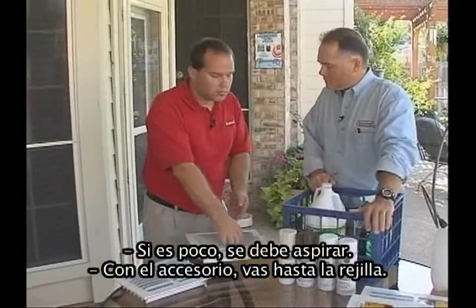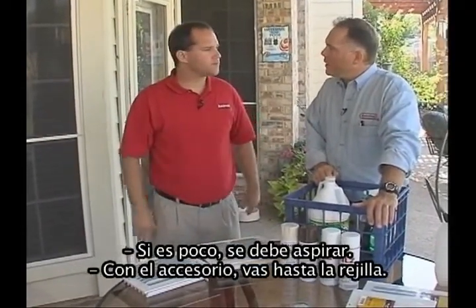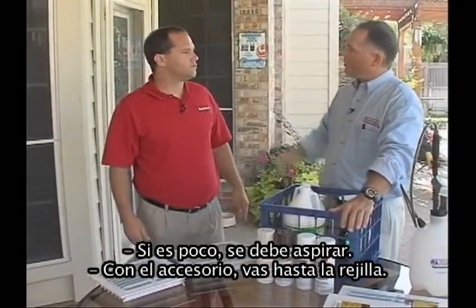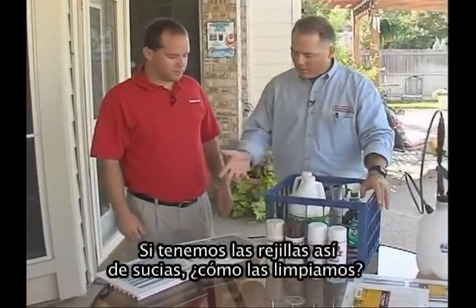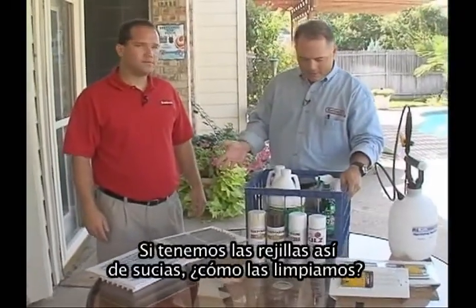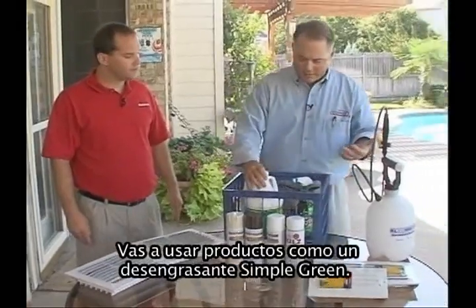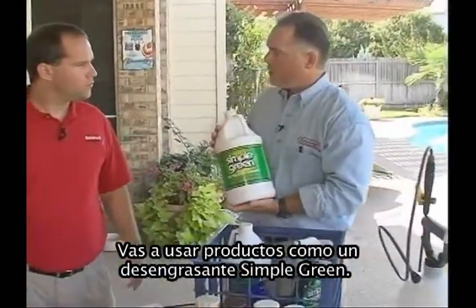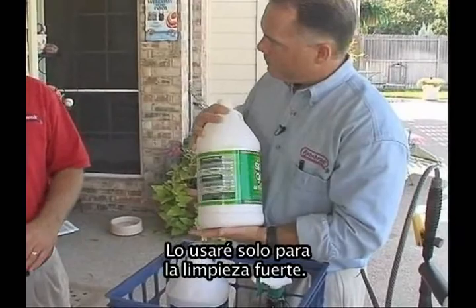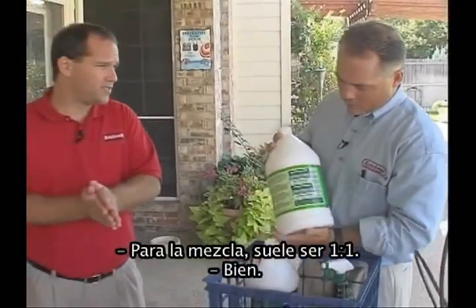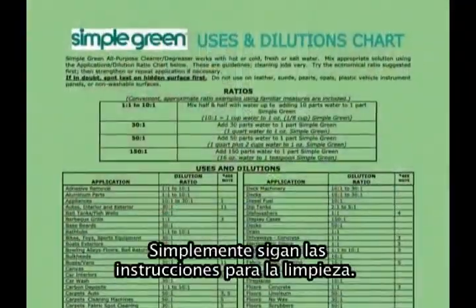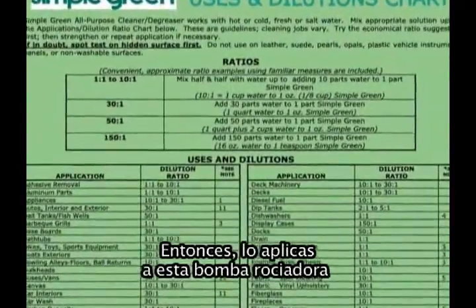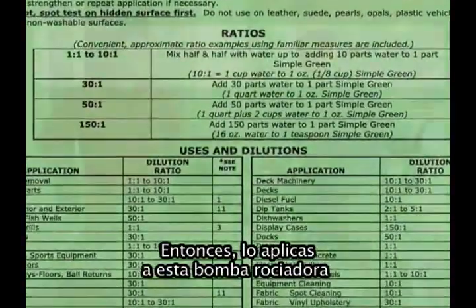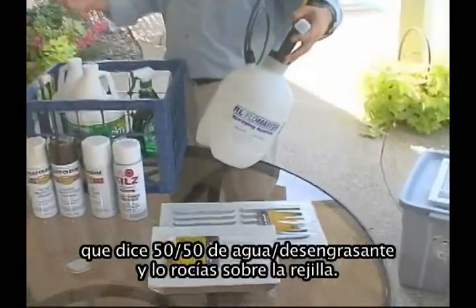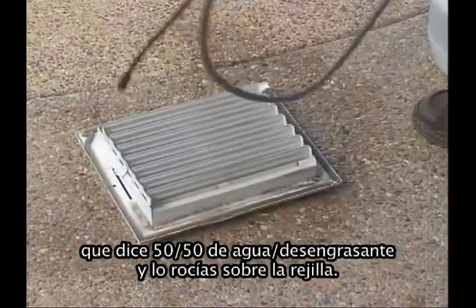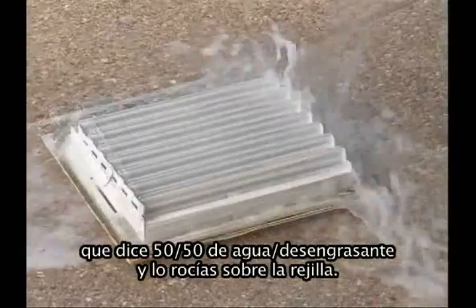If it's just minor, a lot of times you can just do topical vacuuming with the actual shop vac attachments right at the register itself. Exactly. Okay, well, once it is heavy soiling like that, let's talk about cleaning it. You're going to use a product like a degreaser here, a Simple Green product. Yep. And I would just use the heavy cleaning ratio. For the mix, usually it's 1-to-1, but just follow the instructions for the heavy cleaning. Okay, so you apply that right into a pump sprayer here, and maybe let's say it's 50-50, 50% water, 50% degreaser, and you'll spray it right onto the register covers.